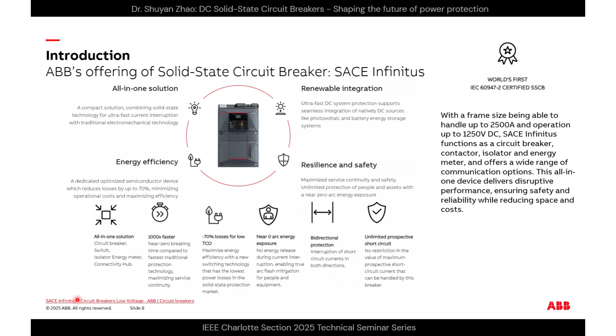Also, of course, it has bidirectional protection, meaning interruption of short circuit current in both directions, and unlimited prospective short circuit. That is actually an important index of any circuit breaker technology, prospective short circuit, and for the solid state version of our product there is no restriction on the value of the maximum prospective short circuit current that can be handled by this breaker. That is actually a really promising technology, and if you're interested, you are welcome to visit the website of this product.